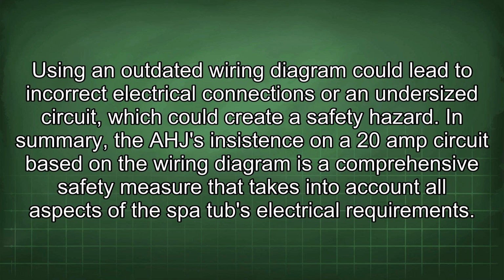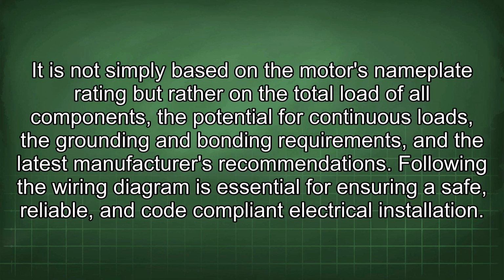Using an outdated wiring diagram could lead to incorrect electrical connections or an undersized circuit, which could create a safety hazard. In summary, the AHJ insistence on a 20 amp circuit based on the wiring diagram is a comprehensive safety measure that takes into account all aspects of the spa tub's electrical requirements. It is not simply based on the motor's nameplate rating, but rather on the total load of all components, the potential for continuous loads, the grounding and bonding requirements, and the latest manufacturer's recommendations. Following the wiring diagram is essential for ensuring a safe, reliable, and code-compliant electrical installation.